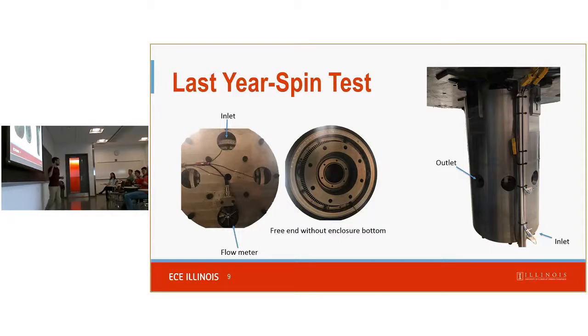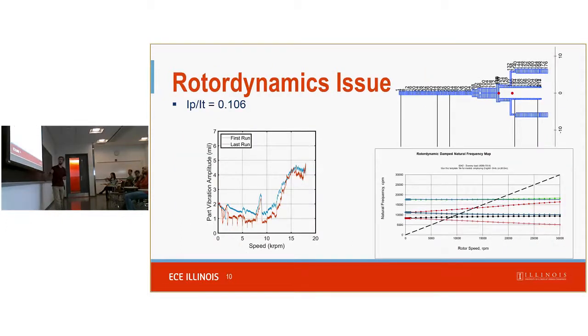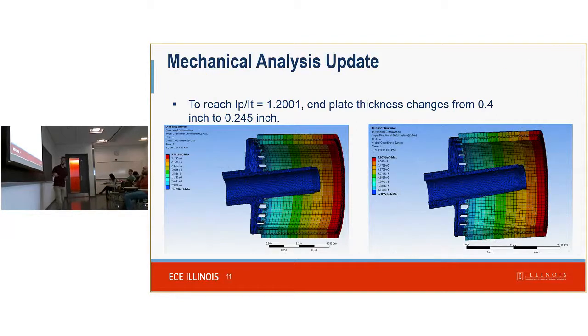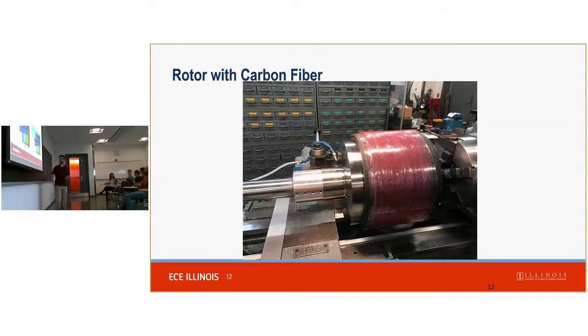Towards the end of just about a year ago, we sent a slightly scaled down model to a company to spin up to full speed, and we got a lot of information from that test. Based on that, looking at the vibrational characteristics, there were some concerns about the amount of vibration we were getting. So the first adjustment after this test was changing the thickness of the end plate. By changing that, we changed the aspect ratio, essentially, of the moment of inertia along different axes, which helps reduce the rotor dynamic or vibrational issues.